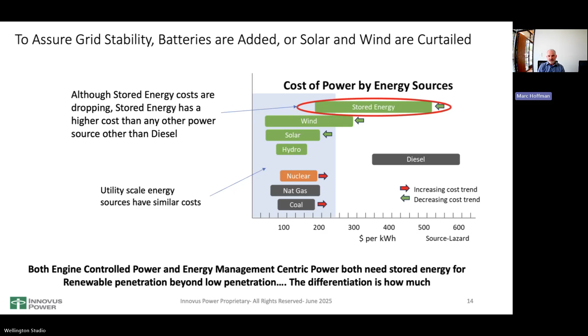When I mentioned a few minutes ago how stored energy has an impact, this is an independent study showing the cost of different energy sources. Depending on scale, this chart is really more for utility scale, but the point is solar and wind have been dropping closer and closer, overlapping with the cost of fossil generation. Other than diesel, which is the worst when it comes to cost per kilowatt hour. But stored energy can be just as costly, so it's very important that whatever stored energy is added to a remote grid, it has to be judiciously added because there's a meaningful cost impact. So when we do our modeling, we pay very close attention to that.